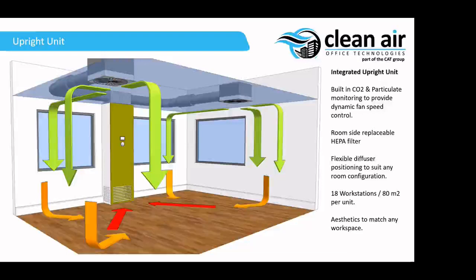One is the noise levels. Another thing is that we wanted to integrate all the controls into a single package that can be delivered to site. So we've been developing this system here, which is the next evolution of it. It sits in the room a bit like a piece of furniture, but it's a fixed installation. Room side, you've got a low level intake, and an attenuator, which dials down the noise from the fan on the intake side. You've then got a much more high efficiency fan than you would get packaged with a HEPA fan filter unit. It then distributes at high level in the ceiling void, or even without a ceiling at all, or with exposed ceilings, through two small diffusers over the space. So it's a much more flexible system.